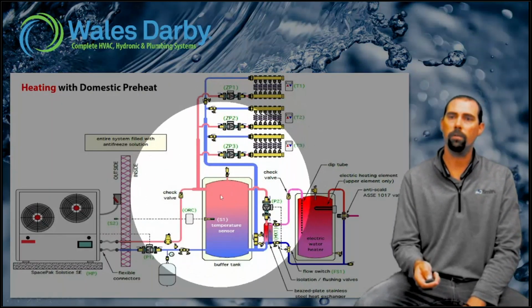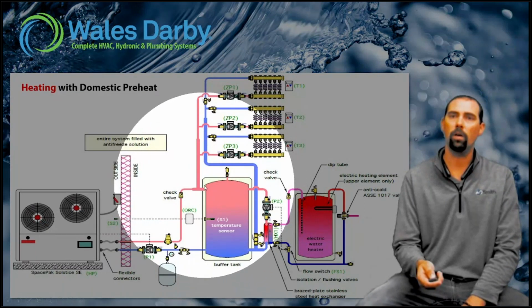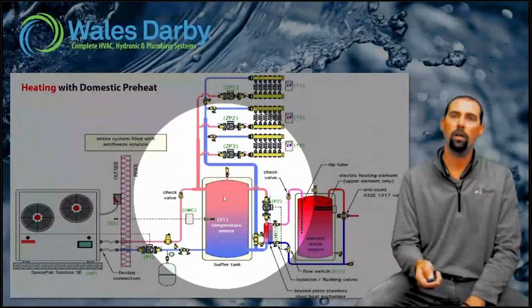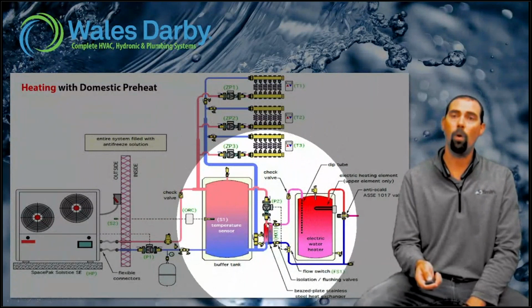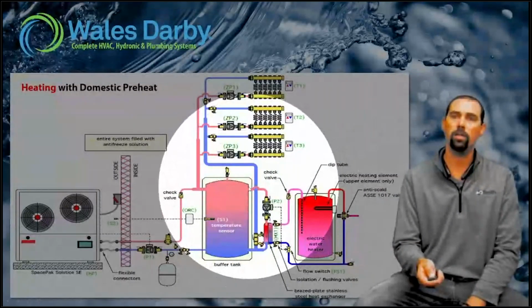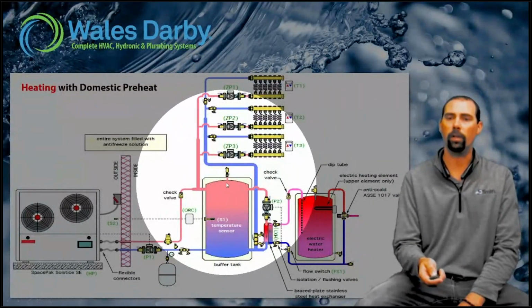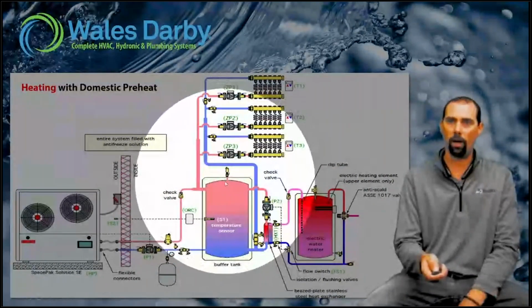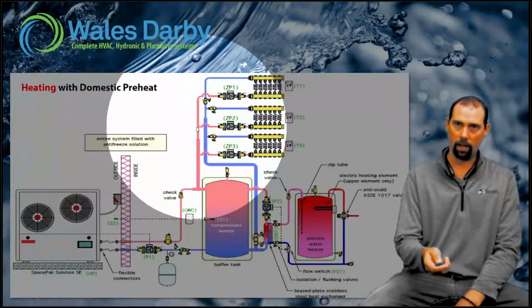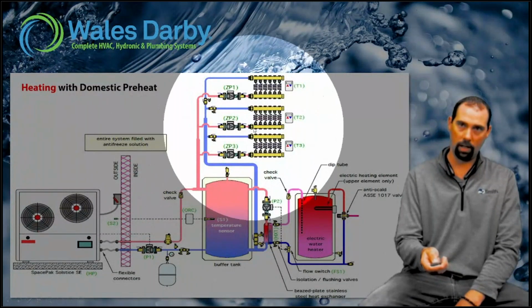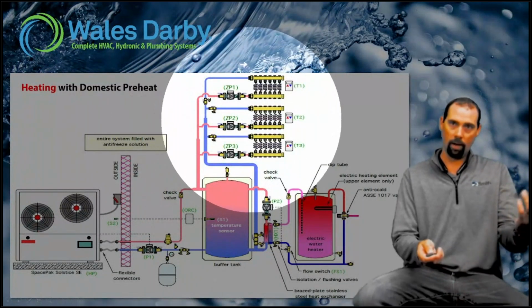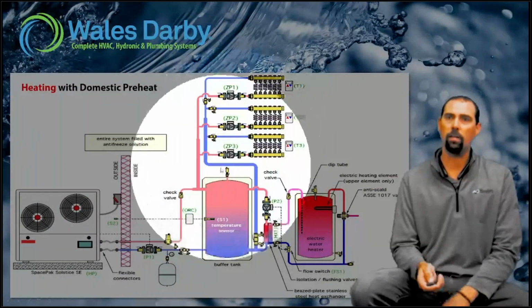There's a bit of a different setup here as far as the piping goes. We're still utilizing a 4-pipe setup on the buffer tank, and there are different configurations depending on your application, as far as 3-pipe or 4-pipe. What we're doing here is taking those hotter temperatures and also feeding right off the top of the tank into our radiant zones. Right here we've got 3 radiant zones.